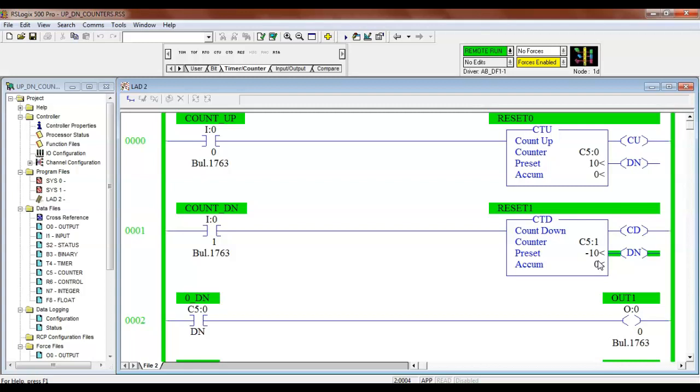So we could start another counter counting, right? You understand? If I've got an overflow, then I could enable another counter and get greater than 32,768. In fact, we usually count in 10s, instead of a weird number, if you don't understand binary, like 32,767. So I might reset it at 20,000 or 30,000, and just stop it and start another counter before it even has a chance to overflow.